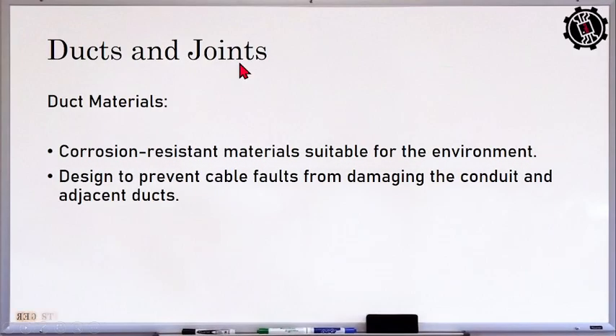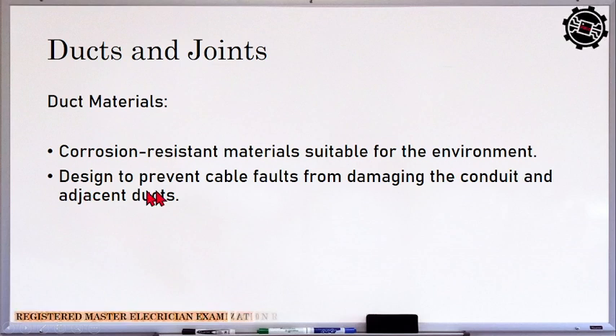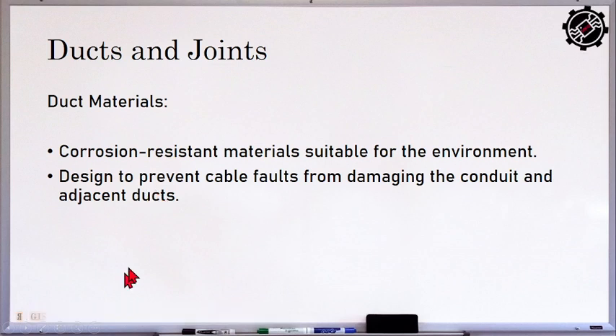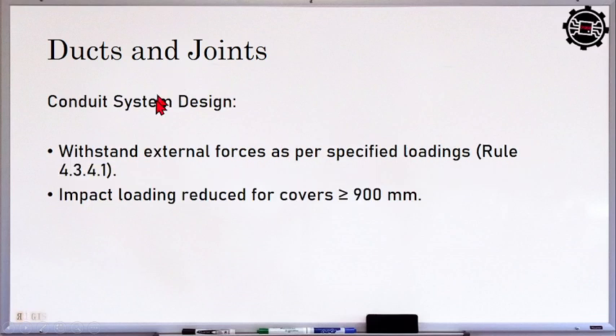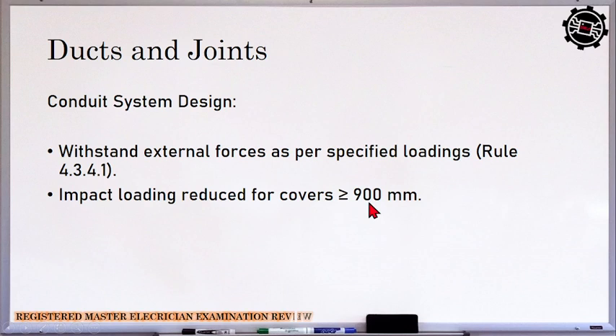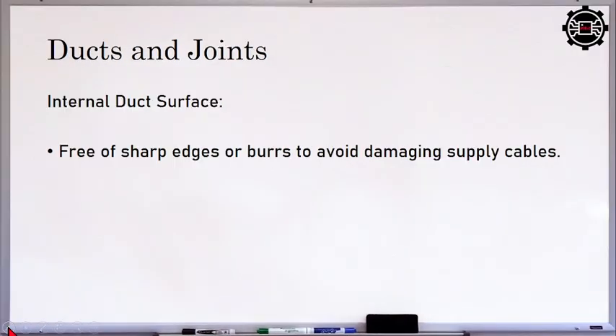Okay, so ducts and joints. So duct materials. So corrosion resistant materials suitable for the environment. Now, if we're going to use ducting sa ating underground system, so dapat it must be stable enough for corrosive environment. So designed to prevent cable faults from damaging the conduit and adjacent ducts. Okay, so the conduit system designed for ducts and joints. So it must withstand external forces as specified by this loading. So impact loading reduce covers, which is greater than or equal to 90 mm, yung kanyang thickness. So that is 900 mm, para hindi 90 mm. Then internal duct surface free of sharp edges or burrs to avoid damaging the supply cable.